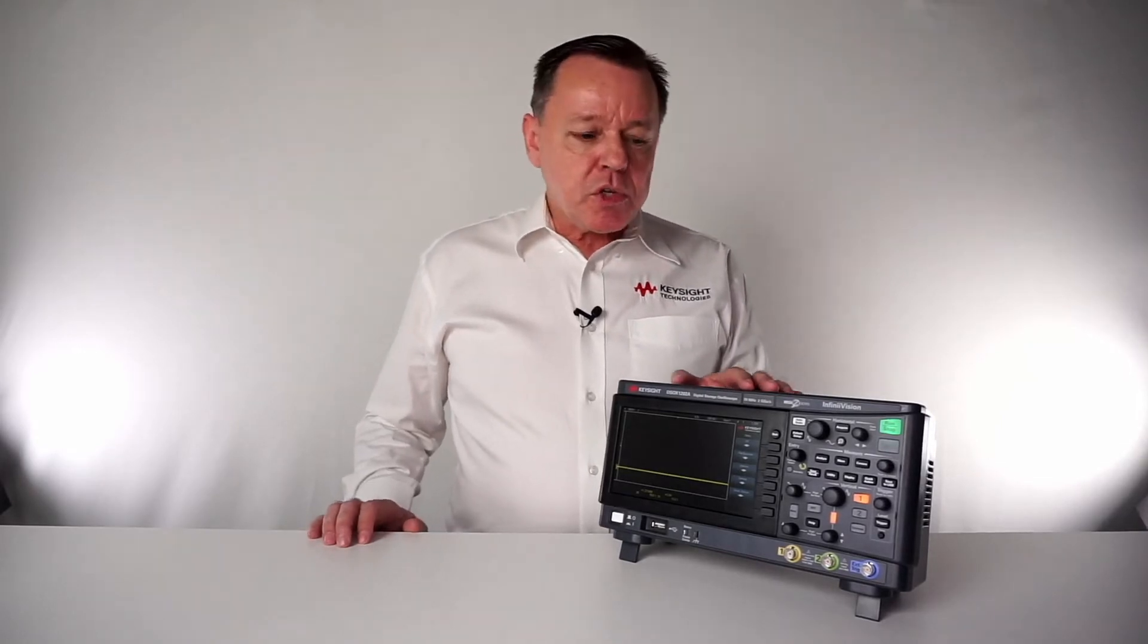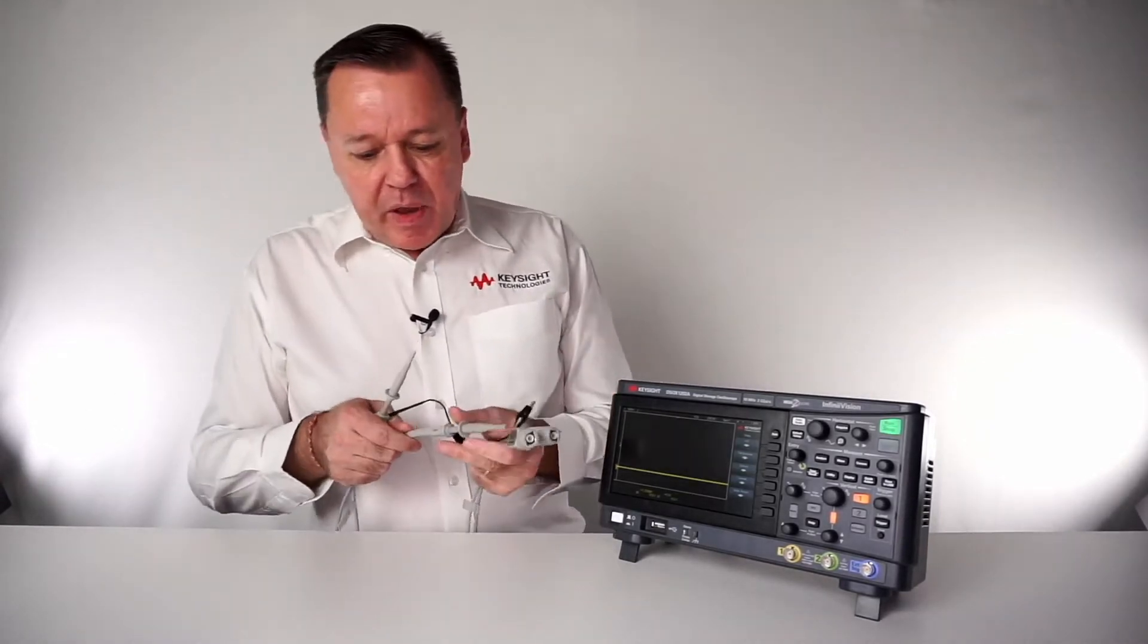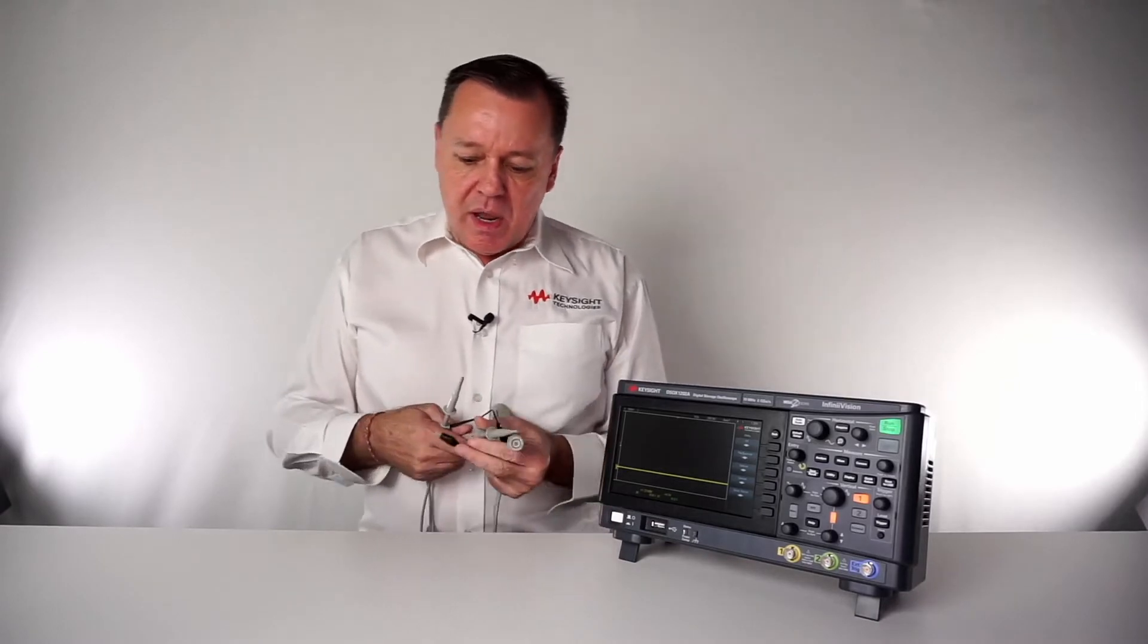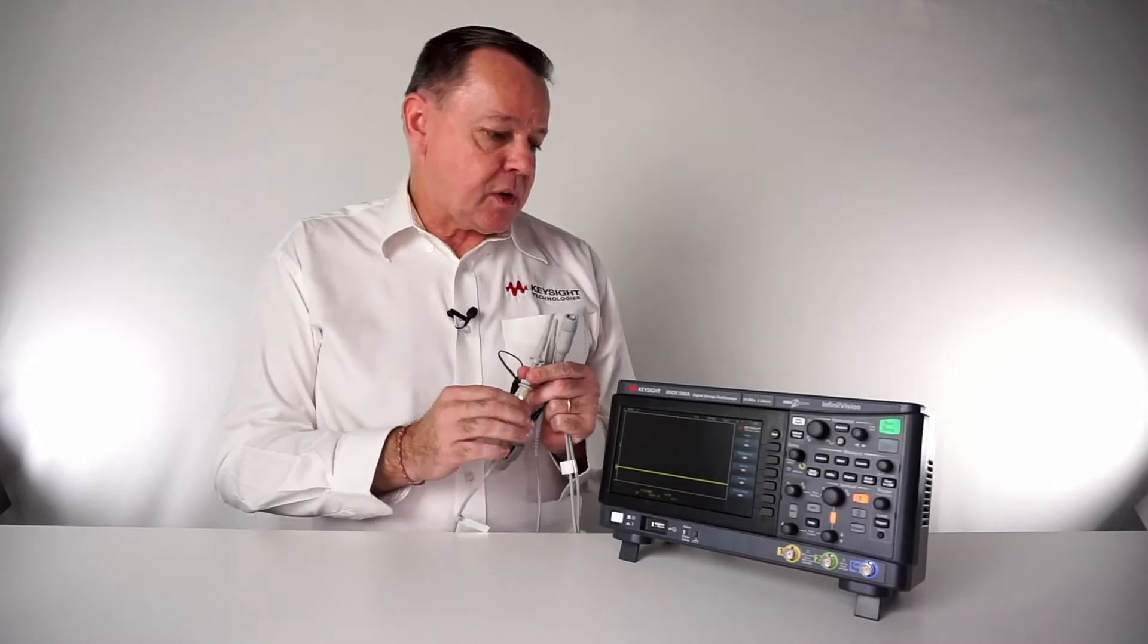What I want to show you today is how to compensate probes. I have here two different probes. One probe has the compensation capacitor here at the BNC connector, and the other probe has it here in the probe itself, this yellow adjustment.